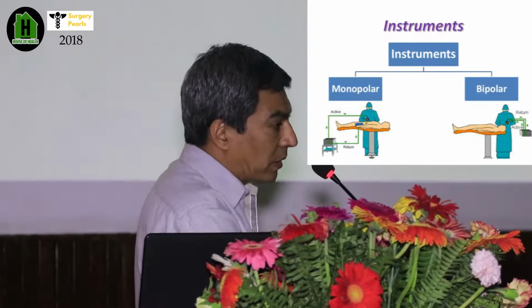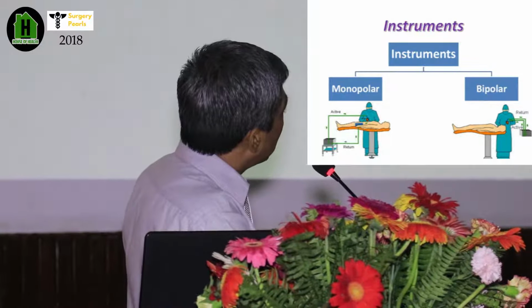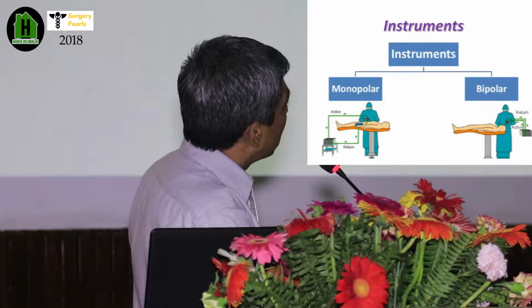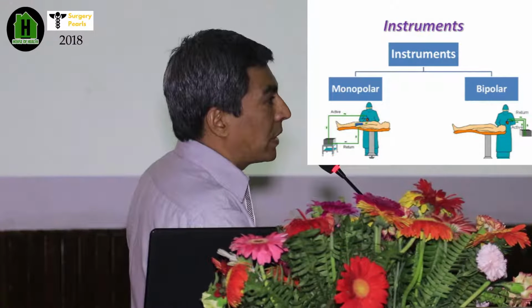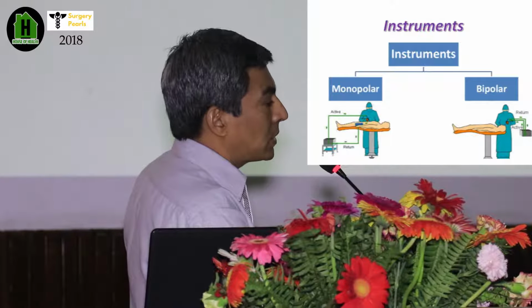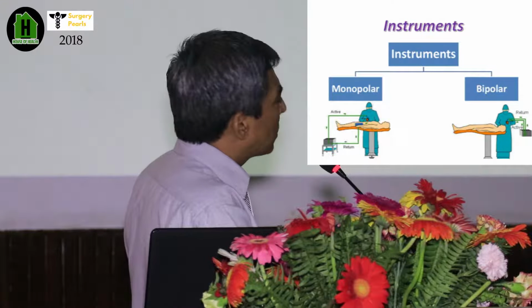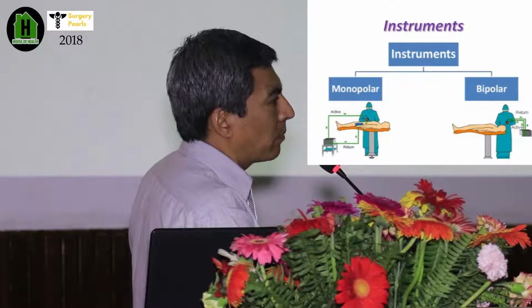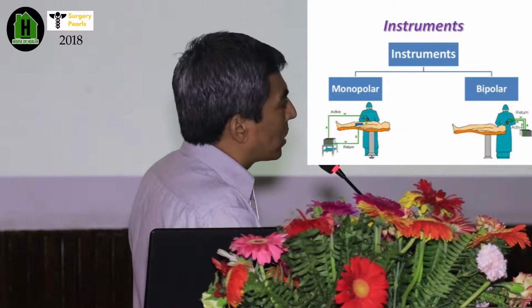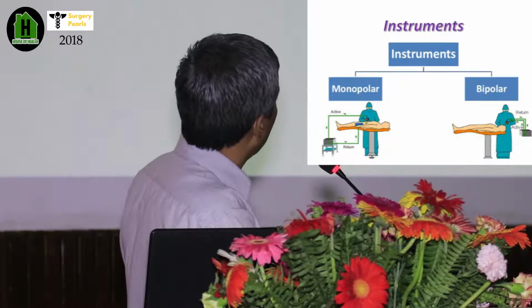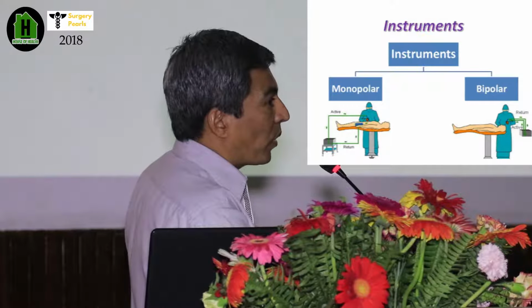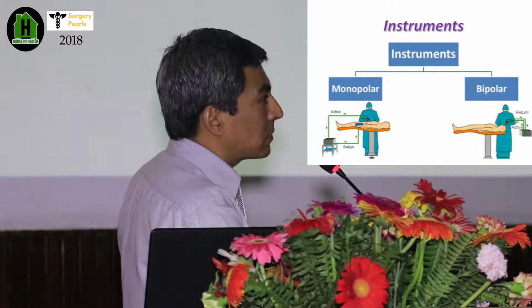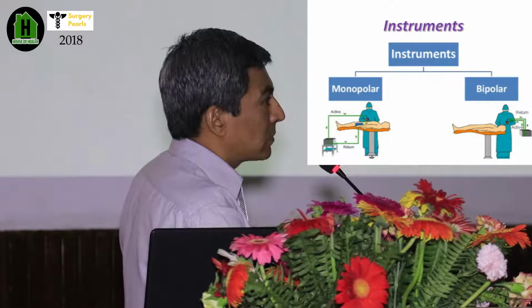Unlike in the monopolar, in the bipolar, so you can see there, the tissue in between the two electrodes is very minimal. The electricity has no need to pass through the whole body of the patient. Again, one more difference I would like to mention here: the monopolar diathermy always needs grounding, unlike the bipolar.